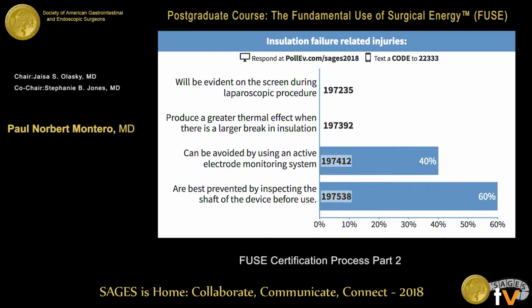As a matter of fact, what we recommend as cues for you is that you assume that every instrument you use has an insulation failure, and that you work in such a way that you always are aware of where your instrument is touching something. That really is the best way to prevent insulation failure. Because even a new device out of the box can have an up to 30% chance that there's a crack in insulation. So you basically avoid insulation failure injuries by assuming that you're working with insulation failure. Make sense?